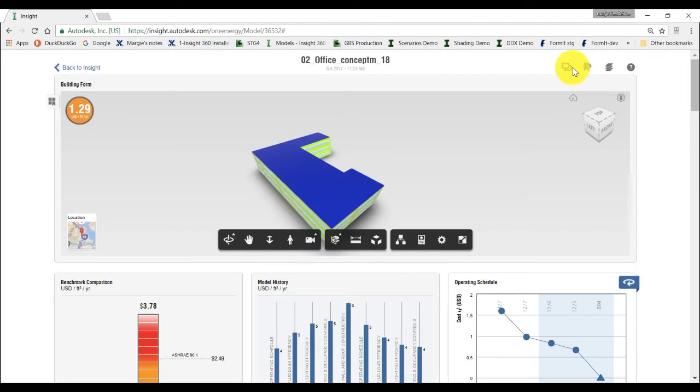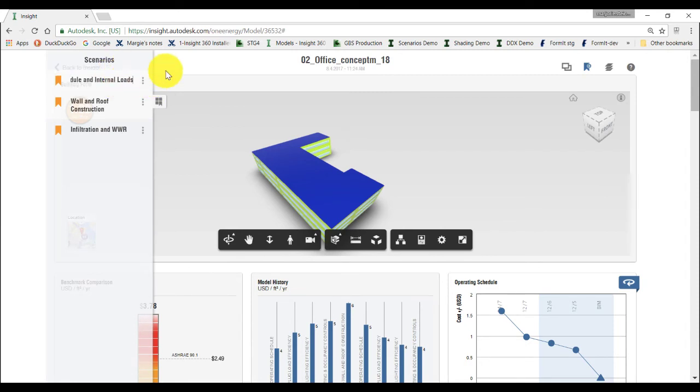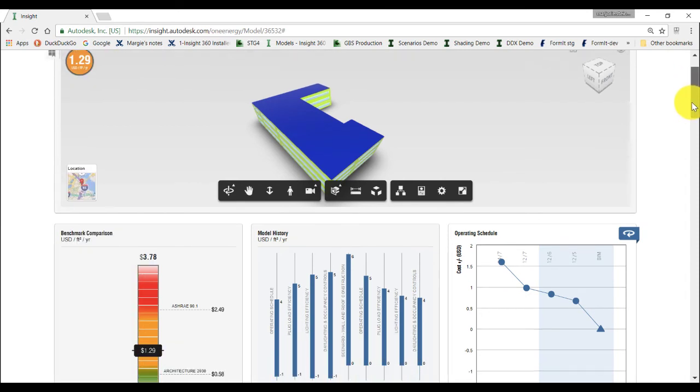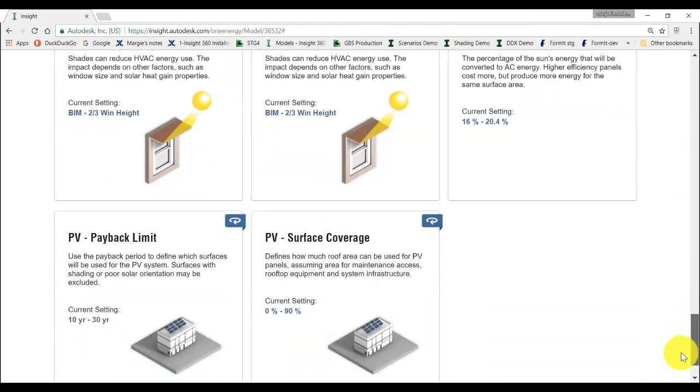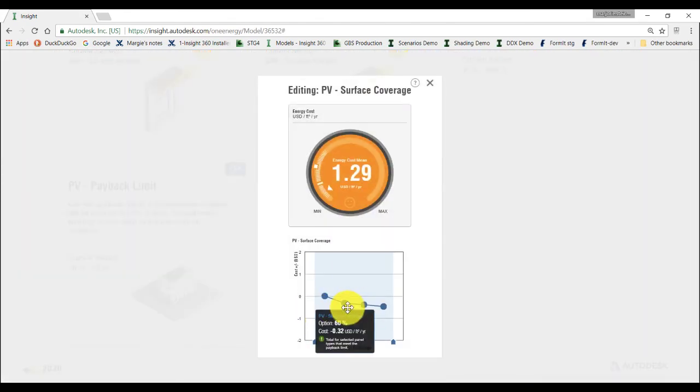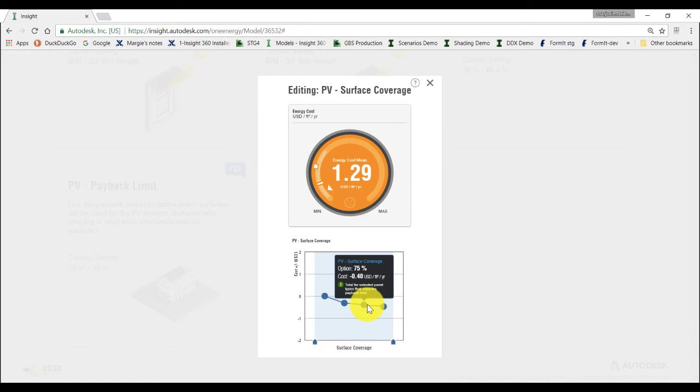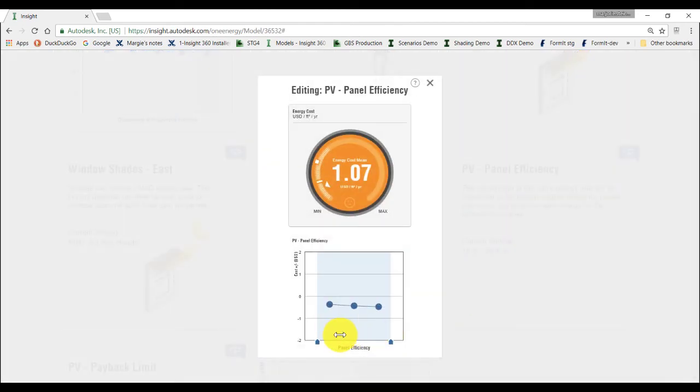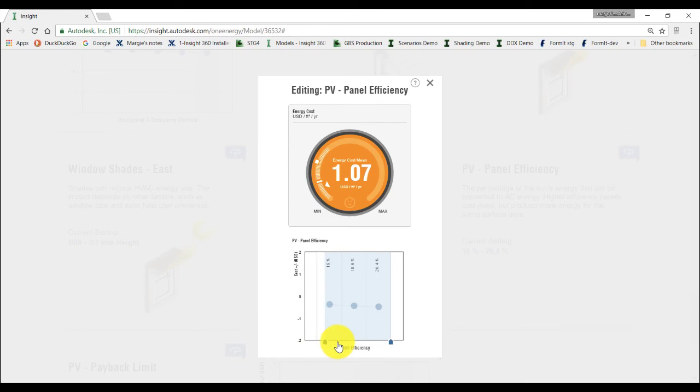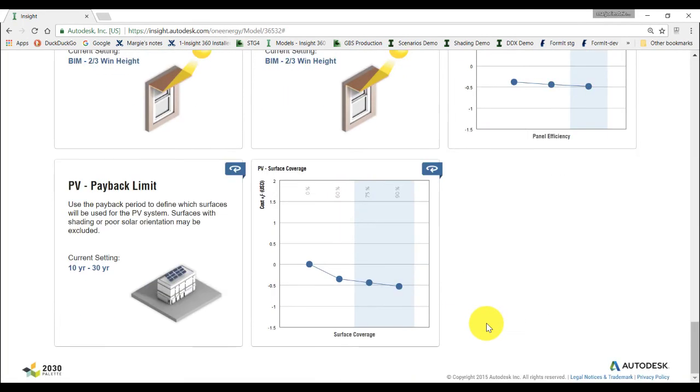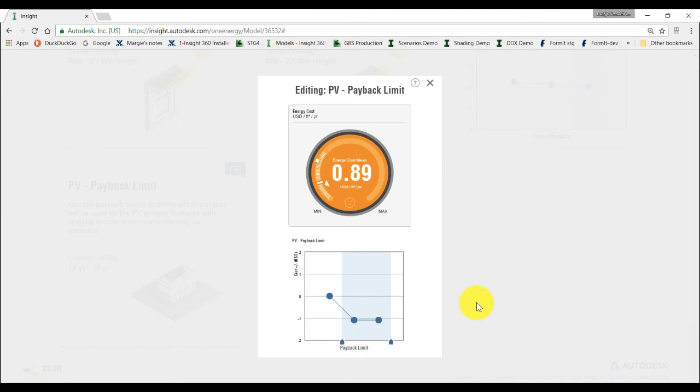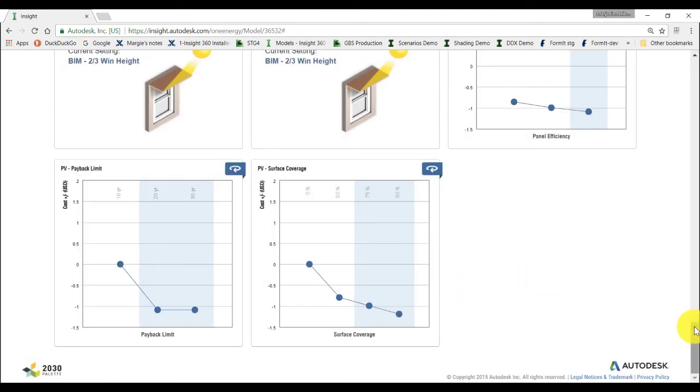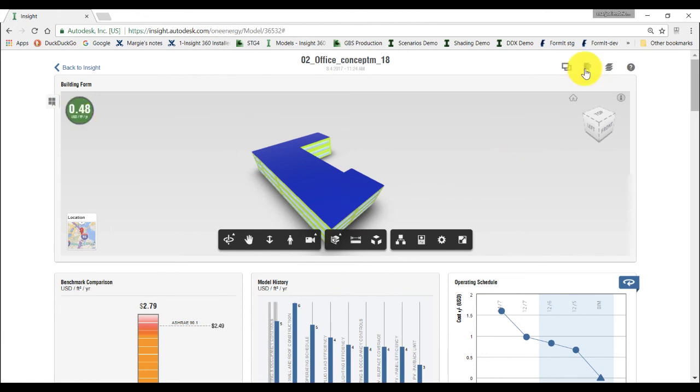Create a Scenario and name it Schedule and Internal Loads. Finally, we'll do one more Scenario to include a photovoltaic system to our project. In this example, we will cover between 75 and 90% of the roof with photovoltaic panels. We choose the highest efficiency panel and will allow a payback period to be between 20-30 years. Notice how the energy cost range has now changed from yellow to green. Let's go ahead and save this Scenario.